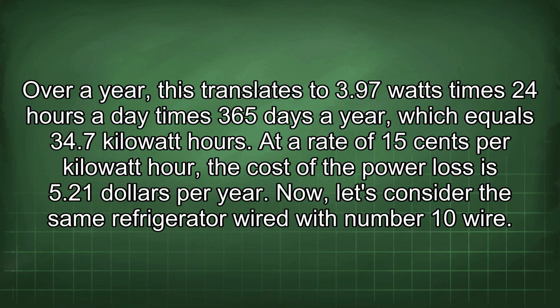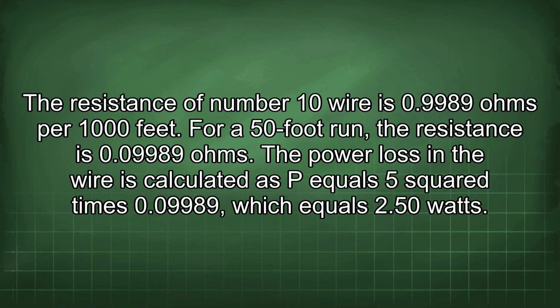per year. Now, let's consider the same refrigerator wired with number 10 wire. The resistance of number 10 wire is 0.9989 ohms per 1000 feet. For a 50-foot run, the resistance is 0.09989 ohms. The power loss in the wire is calculated as P equals 5 squared times 0.09989, which equals 2.50 watts.